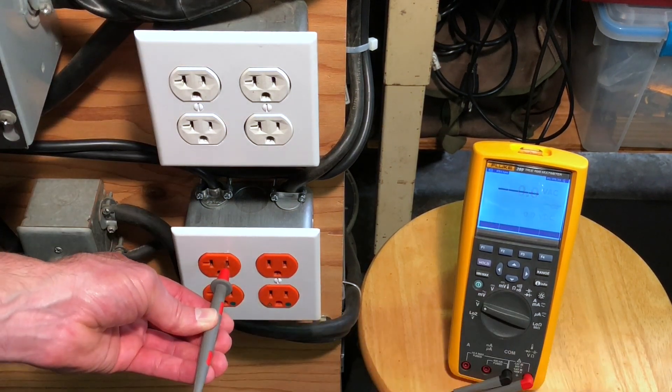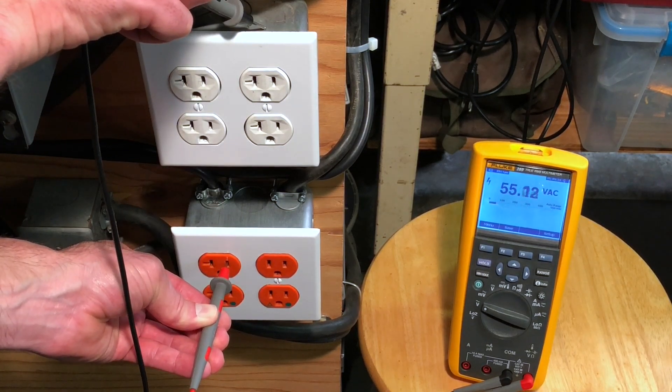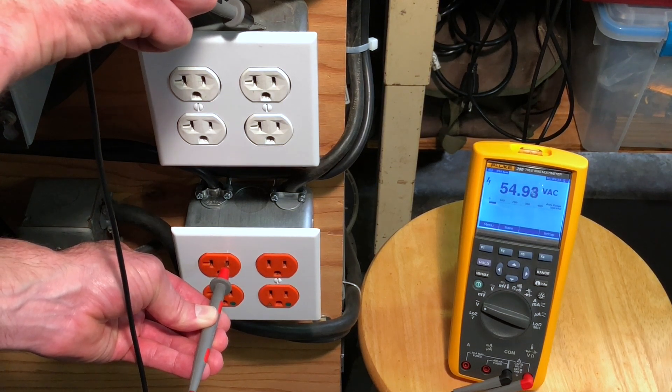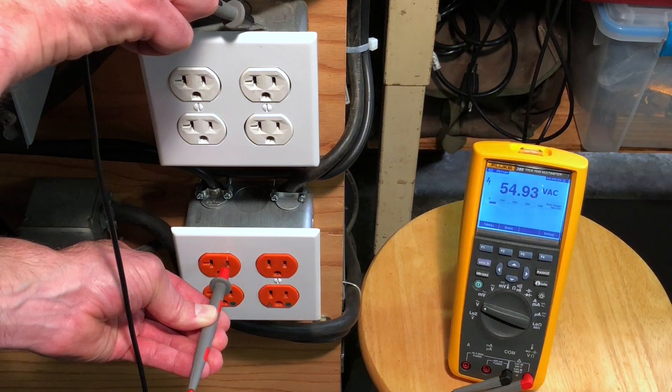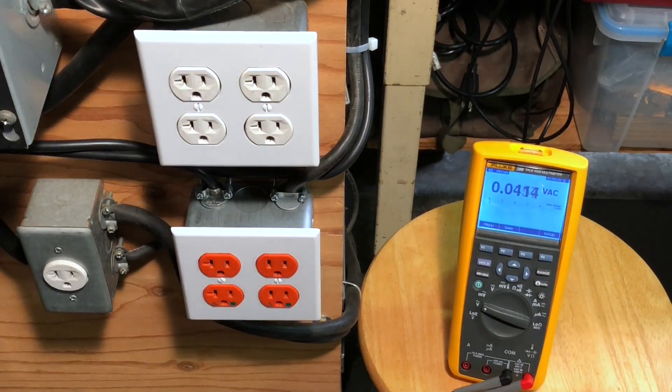If I just go back like so, there's that ghost voltage again. Really simple as that. When you see that change, and it goes from the voltage reading and then disappears on the low impedance mode, you know that reading you were getting was in fact a ghost voltage.